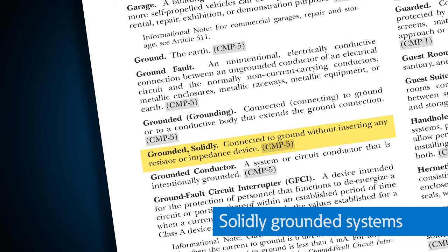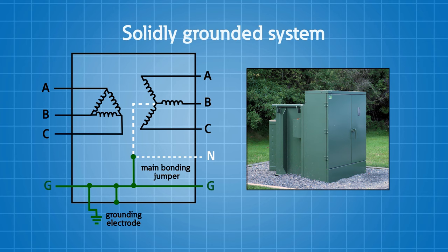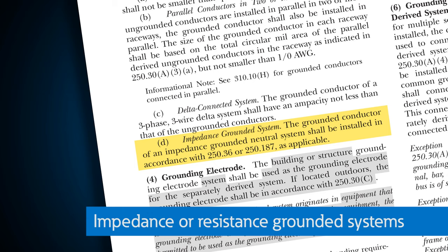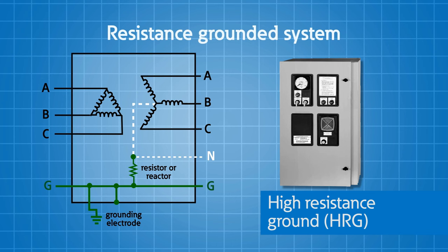Everything we've talked about so far has been about grounding and bonding of components and electrical systems, establishing that connection at the service or at our separately derived system between the grounded conductor, equipment bonding, and earth. Now we're going to talk about system grounding: solidly grounded systems versus resistance or impedance grounded systems. Solidly grounded means there's a solid connection to earth at some point in the power distribution system with no resistor or impedance inserted. Ungrounded systems have no connection to ground at all. Impedance or resistive grounded systems are connected to earth through an impedance.